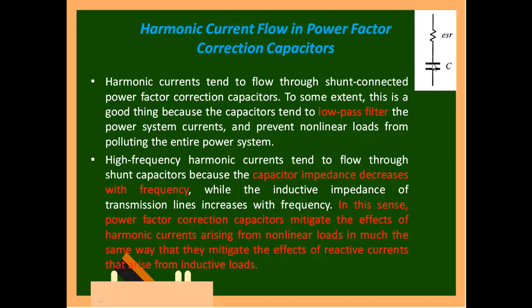So if this current is flowing in this capacitor, then obviously it will start heating. That is what we are going to see here. To some extent this is a good thing, because the capacitor tends to low pass filter the power system current and prevent the non-linear load from polluting the entire power system. But this is okay only to some extent. What we say is higher order harmonics.